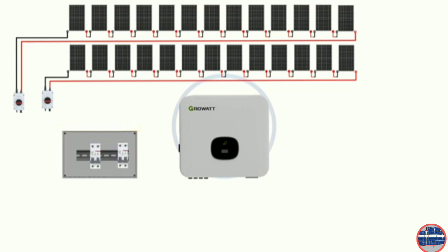A DC distribution board is a panel that houses DC circuit breakers, MCBs, surge protection devices (SPDs), and other components to distribute DC power safely and efficiently. Calculating the size of a DC MCB involves determining the appropriate current rating to protect the circuit from overcurrent and short circuits. Here's a breakdown of the formula and the factors to consider. For a solar string with an Isc (short circuit current) of 14 amperes, the recommended DC circuit breaker size would be 20 amperes. Here's the calculation.